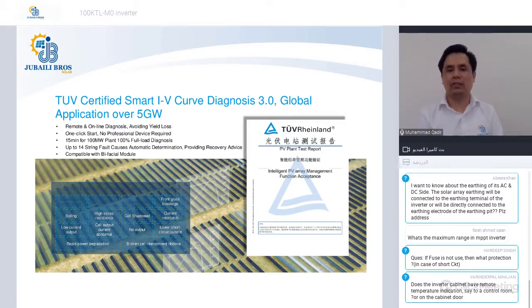So from the click of your instruction till the time it gives you the report is taking only 15 minutes, which is a very short period of time. And also this scanning of the PV string happens 2 times in order to make sure of the reliability of the scan. This IV curve diagnosis can check up to 14 different string faults, such as swelling, low current output, rated power degradation, cell shadowed, and many others.